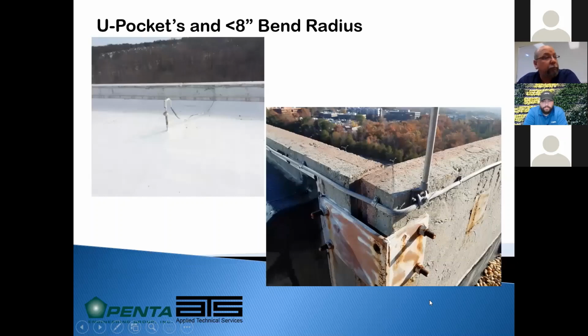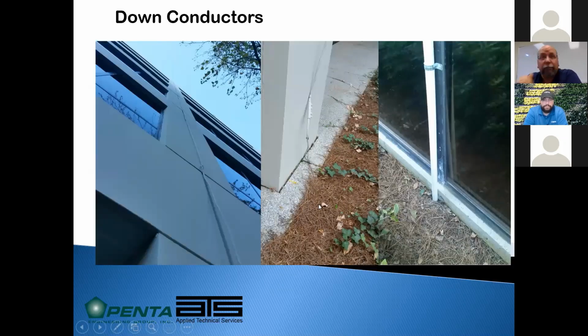So Steve, out here in Colorado, would snow be a reason for protection like that last picture? If you're going to be shoveling the snow, basically you're trying to protect the strands of the cable from getting nicked and cut to make sure that they all stay intact. So it's more of a physical damage. Snow itself, freeze, melt, thaw, is not going to really damage the cable. It may separate the strands over time, but in general, we're really dealing with more physical activity. So if it's in an area where you may be having to shovel and you might be banging it with a shovel, it should be protected.